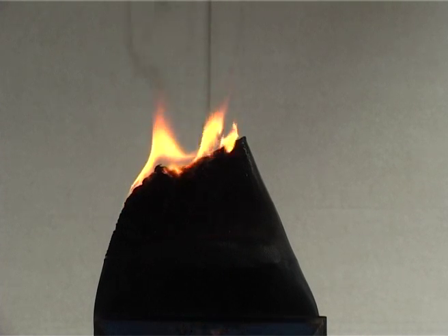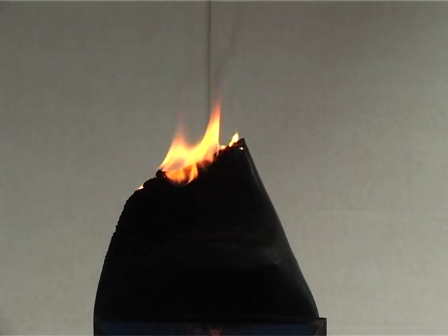This is clearly not LSF. In addition, glands that these shrouds are generally supplied with are inferior in both design and brass content, causing badly fitting components and poor earthing capabilities.